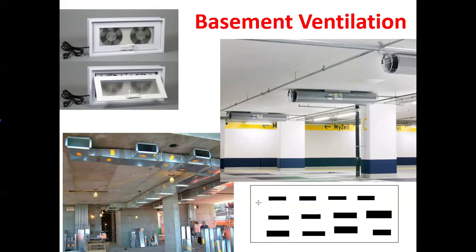Okay. So here, what will actually be happening? It draws the air at a certain extent, and it discharges the air approximately a distance of 30 to 40 feet. At the same extent, you will have the other jet fan. So this is how they spread the fresh air. At the same time, the existing air is gradually sucked out along the way, and it is reverted back to the atmosphere once again. So this is the concept of a jet fan assembly.